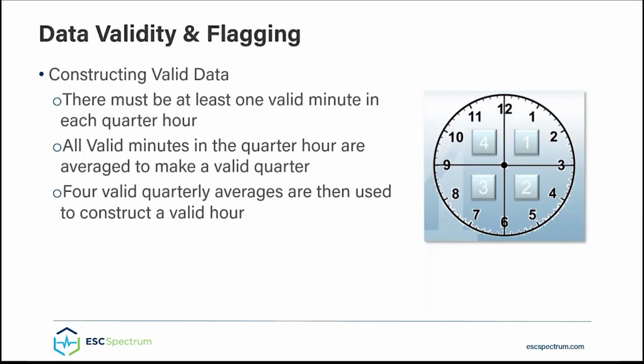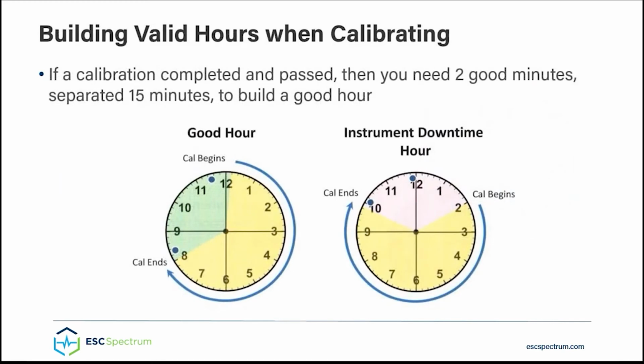Different rules apply when your system is in calibration, so let's take a look at an example. In order for the hour during which calibration occurs to be valid, you must first complete and pass the calibration, and second, record two good minutes separated by at least 15 minutes. So on the left side, the hour was valid because following successful completion of the calibration, we were able to get a good minute in the third quadrant and in the fourth quadrant, separated by 15 minutes.